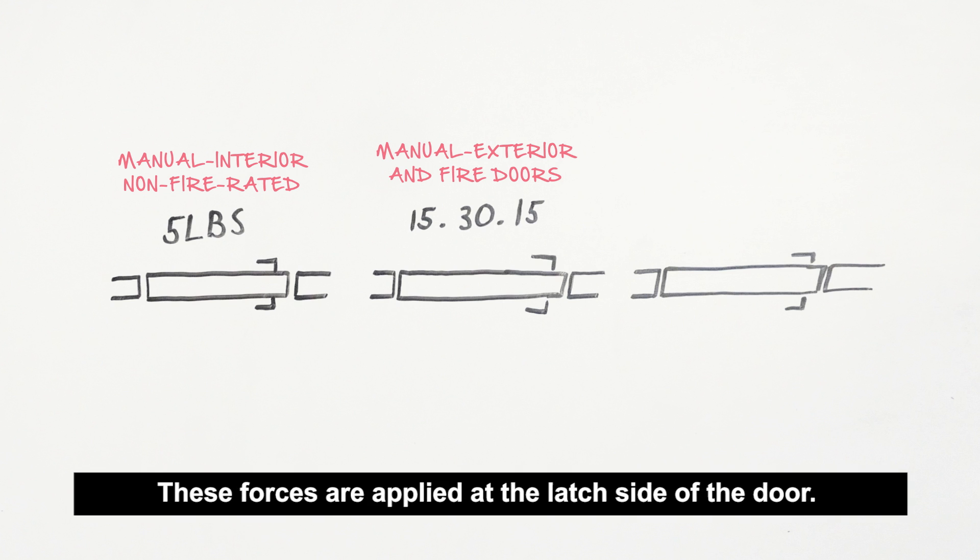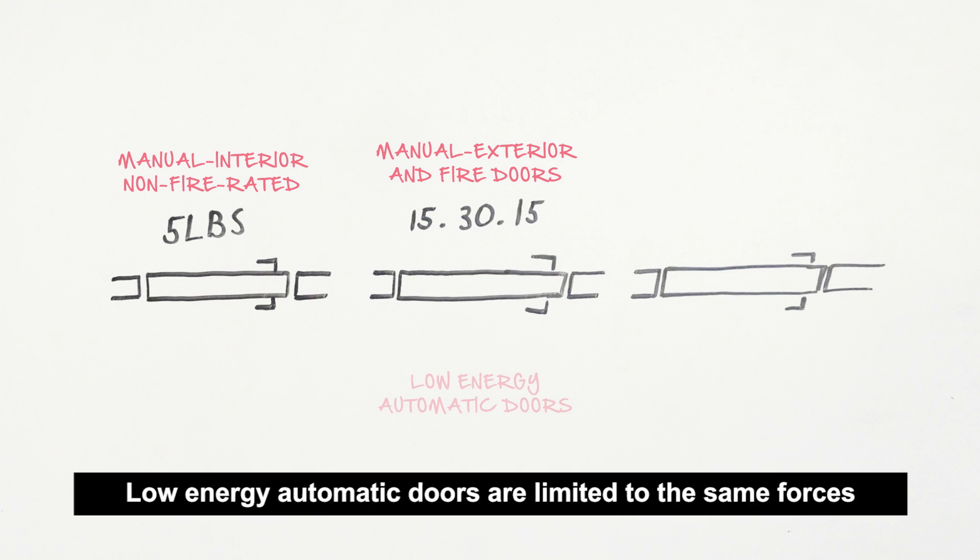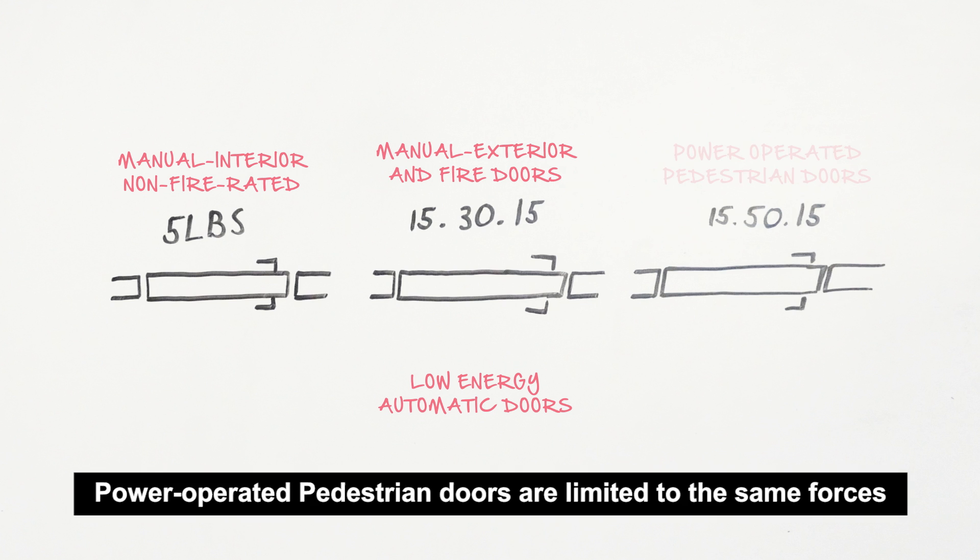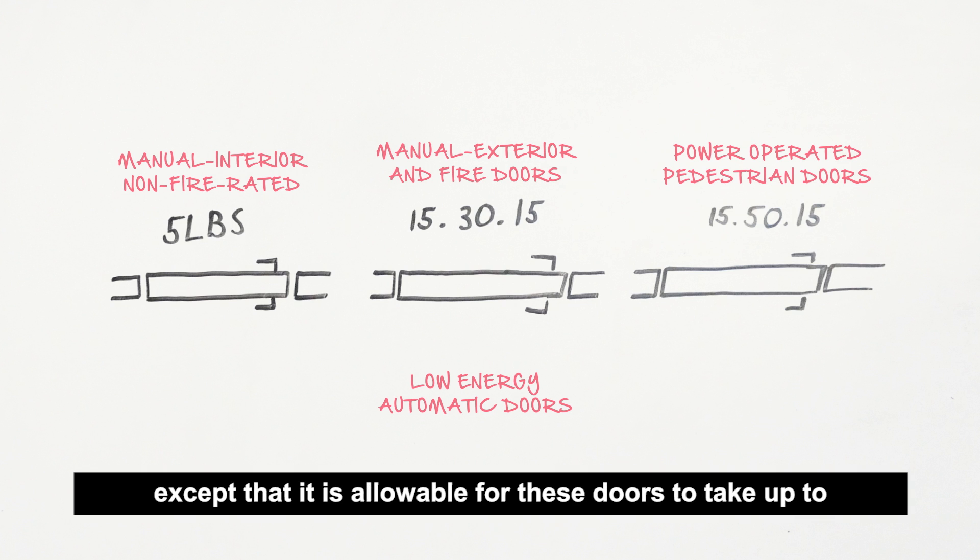These forces are applied at the latch side of the door. Low energy automatic doors are limited to the same forces as manual exterior doors and must meet ANSI BHMA 156.19 requirements. Power operated pedestrian doors are limited to the same forces except that it is allowable for these doors to take up to 50 pounds to set the door in motion. Power operated pedestrian doors are required to meet the ANSI BHMA A156.10 standard.